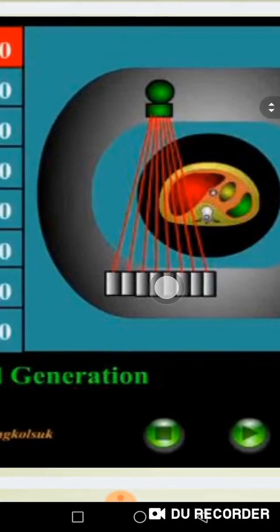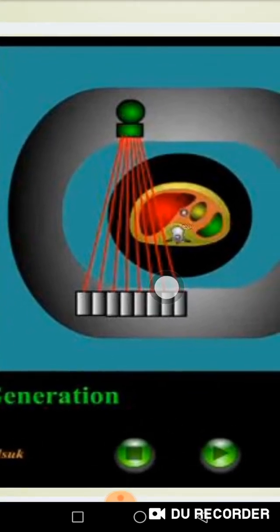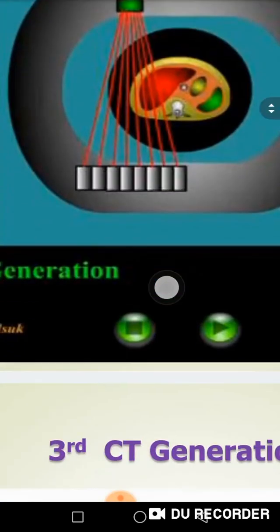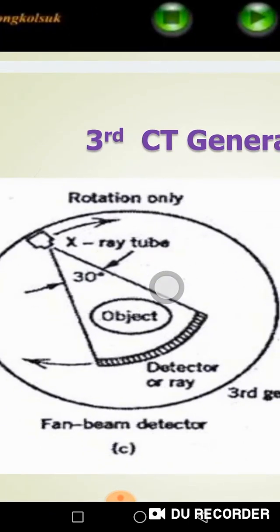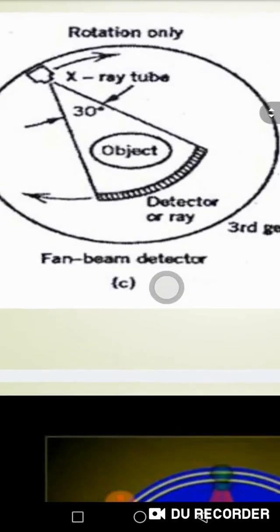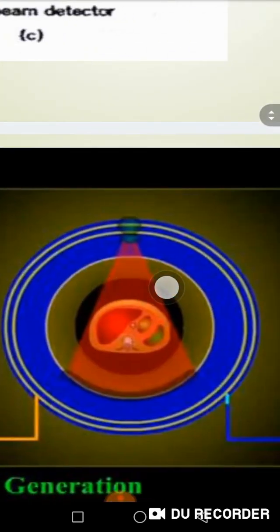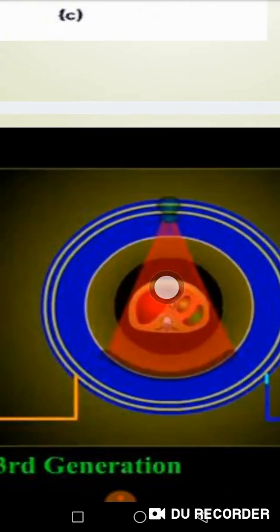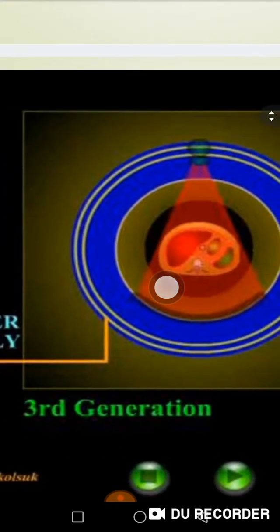The idea is that I need to rotate around the slice to cover this section from all sides and eventually produce an image. The third generation says: make the beam larger, make the rotation larger — it can reach 800 to 900 detectors — and make the fan beam larger. This is called the third generation and is what most devices operate on.